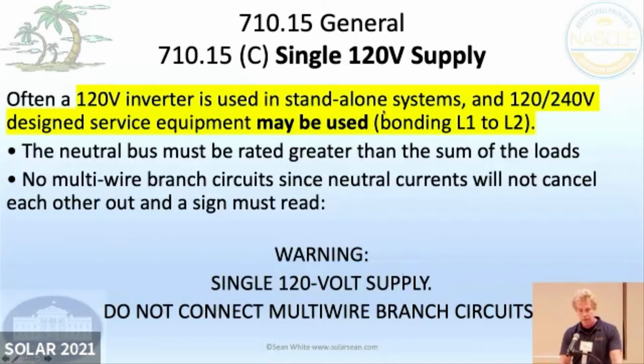And now what we have here is, this is just for a standalone system, a special rule that we've had in there for a long time. What happens a lot of times is people have a 120 volt inverter for off grid. And you go to the electrical supply store, and they're not selling you 120 volt equipment. So you get 240 volt equipment, and you make line one and line two, you just bond them together. So they're at the same voltage. So then there's a problem, because it's possible that you could overload the neutral, because all of a sudden, instead of line one to neutral and line two to neutral opposing each other, in this really creative thing that we call split phase that we just have in the United States, the neutral only carries unbalanced currents. And so if you're balanced, coming out of the inverter, that neutral has 0 on it.